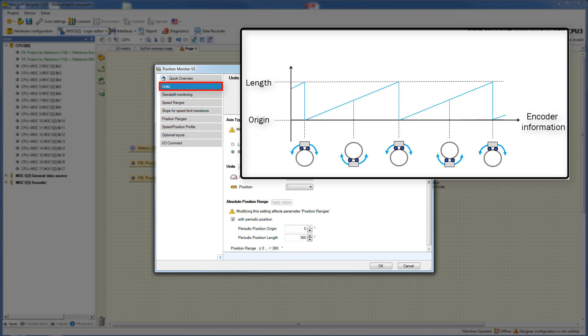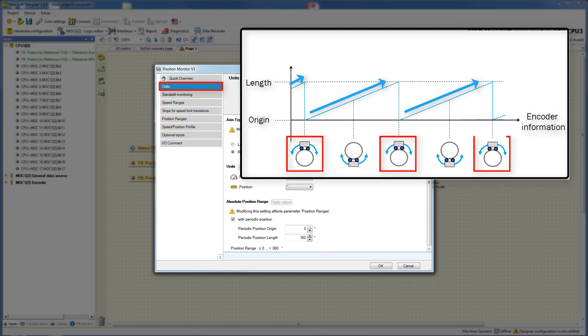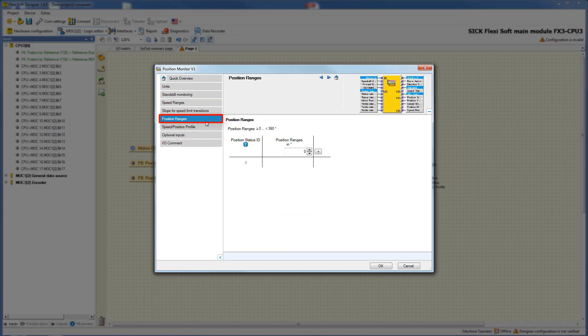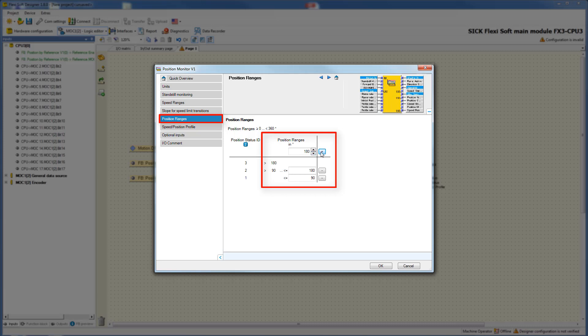After passing the configured length, the cam always returns to the defined origin. For the function safely limited position, the tab position ranges is relevant. In the next step I will demonstrate how to configure these ranges. There you can type your desired position ranges, and by clicking the plus button the defined position range is saved. In this way up to 62 position ranges can be configured. Depending on the area in which the drive is located, the associated position status ID is produced at the output position status ID.